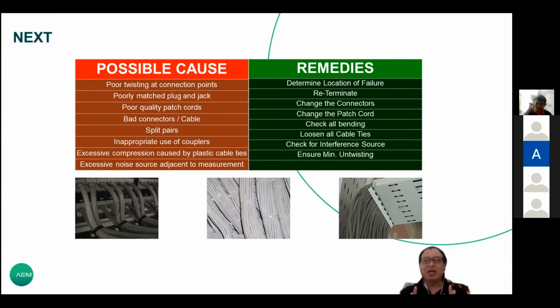Sometimes your cable tie could be too tight, so-called squeezing the cable. Imagine inside the jacket there are 8 wires, 4 pairs. Imagine the 4 pairs being squeezed together tightly, with no space in between. It can cause interference between each pair and create high crosstalk. So if your cable tie is too tight, make sure you loosen it. Sometimes when you do termination, you untwist your cable too much, and then it can also cause crosstalk.